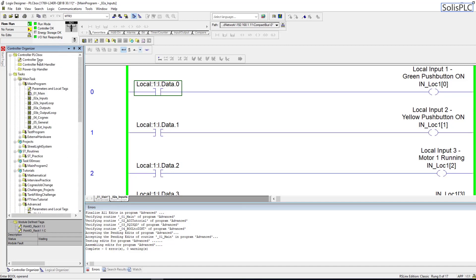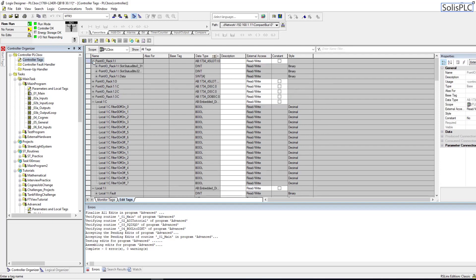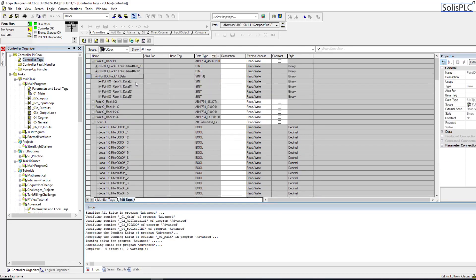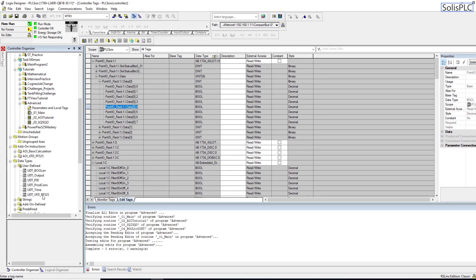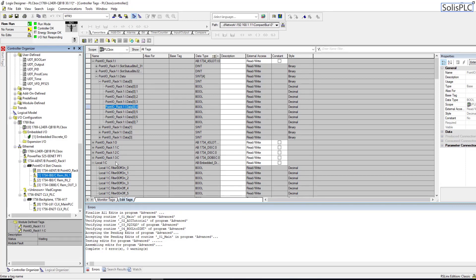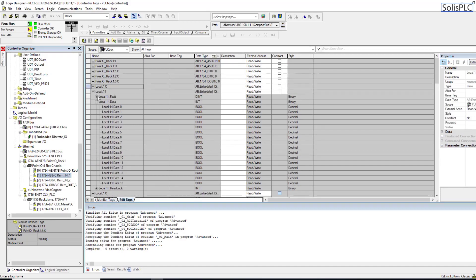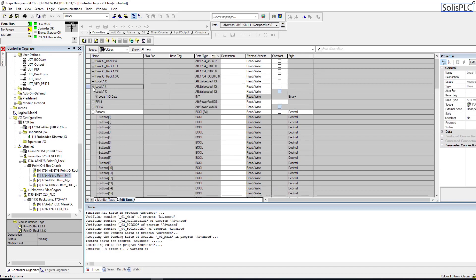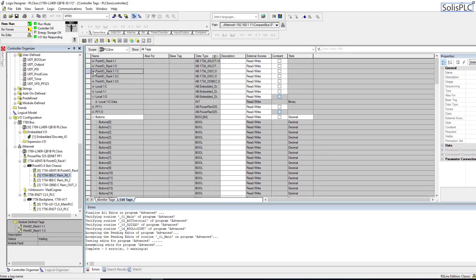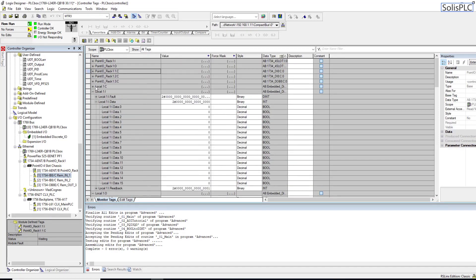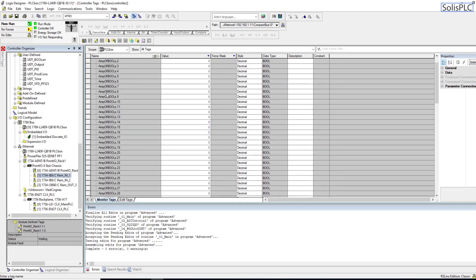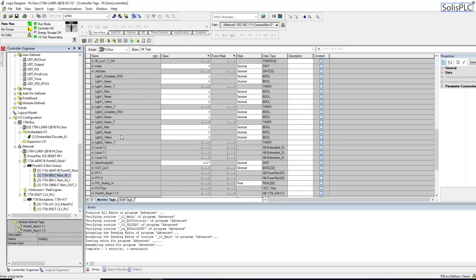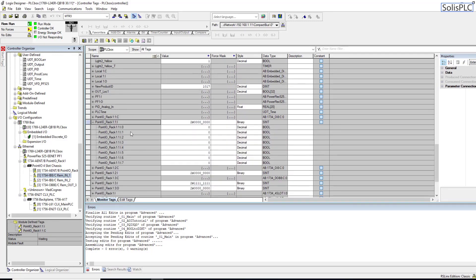Let's look at what the tags are. Point_IO_Rack_1 and then the input. Here's the data - you're going to get multiple points of inputs. Let me double check - I think there should only be eight. Yeah that's correct, so it's a 1734-IB8. I'm going to rearrange them in order so I've got my Point_IO_Rack_1:1:I so here they are - these are the eight booleans that are going to be coming into that tag.